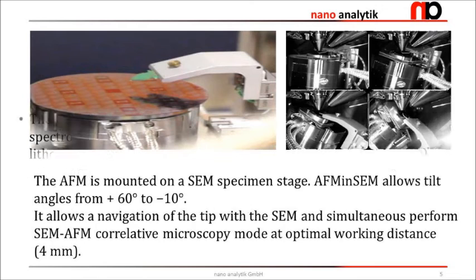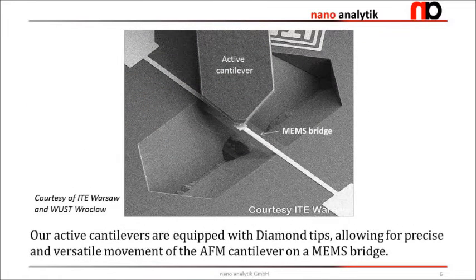The AFM is mounted on an SEM specimen stage. AFMinSEM allows tilt angles from 60 degrees to -10 degrees. It allows a navigation of the tip with the SEM and simultaneously performs SEM AFM correlative microscopy mode at an optimal working distance of 4 millimeters. Our active cantilevers are equipped with diamond tips, allowing for precise and versatile movement of the AFM cantilever on a MEMS bridge.